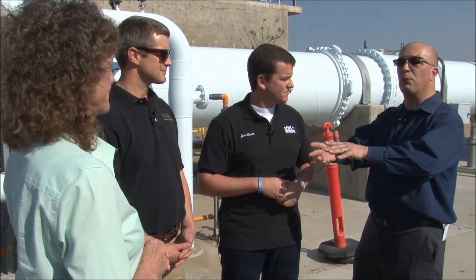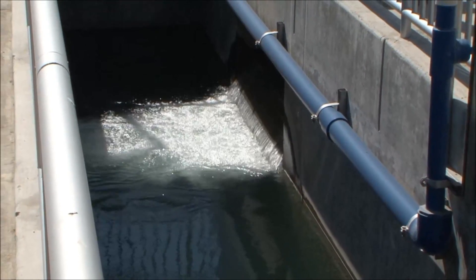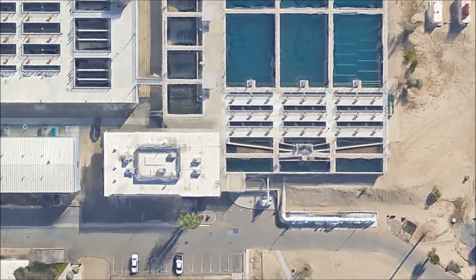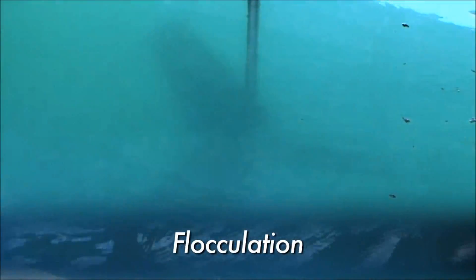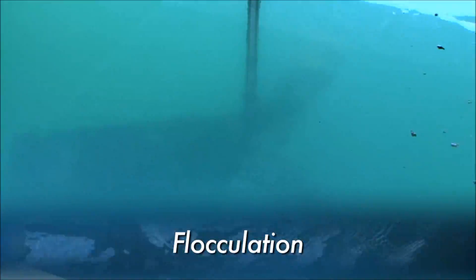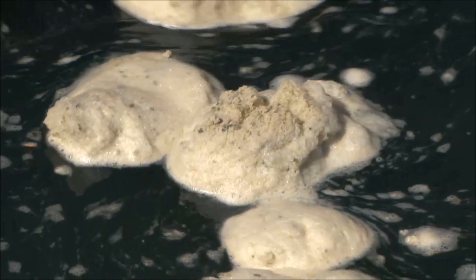We're following the flow of the water through the entire treatment plant. Once it hits this flash mix, what's the next stop? After the chemicals are introduced, it goes into each one of the treatment trains — we have two treatment trains. The next stage is what we call flocculation. At that point, we have flocculators, which are mixers, and they help mix the floc so that we get the biggest, heaviest floc possible by the time it hits our sedimentation basins, which is where we want the floc to fall.